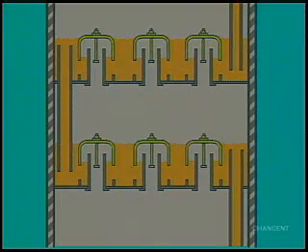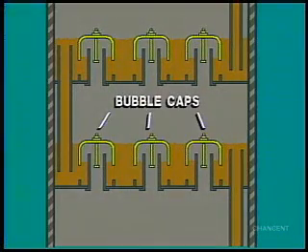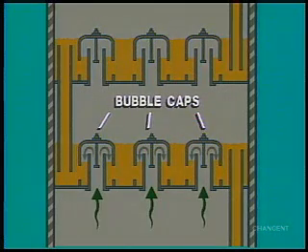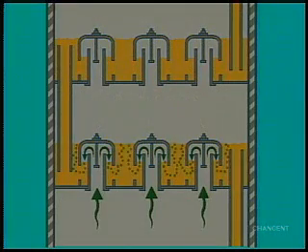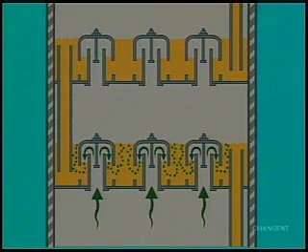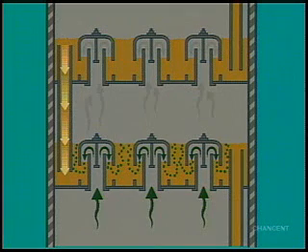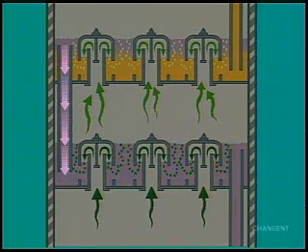Each tray has openings with bubble caps bolted over them. The upflowing gas is forced through these caps and bubbles evenly through the downflowing glycol. The gas gives up water and becomes drier as it passes upward through each succeeding tray. The glycol becomes more saturated with water as it flows downward over each tray.